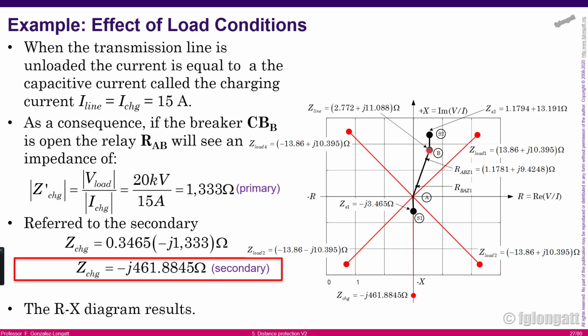But the other relay is at 80% of the impedance, but is looking from B to A. That is the reason that the other point here, the point defined in the zone 1 of the relay BA, is located at 80% of the impedance, but in the other direction. Okay, now there is just a consideration. Okay?